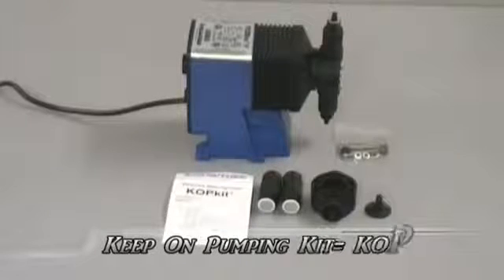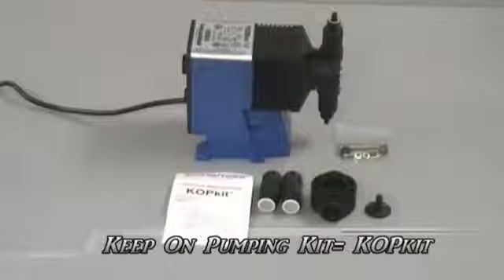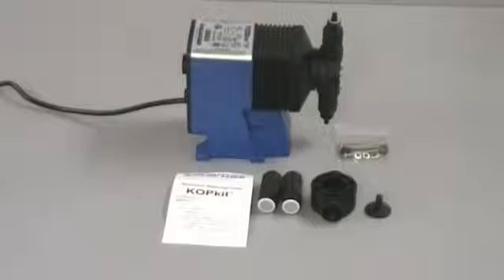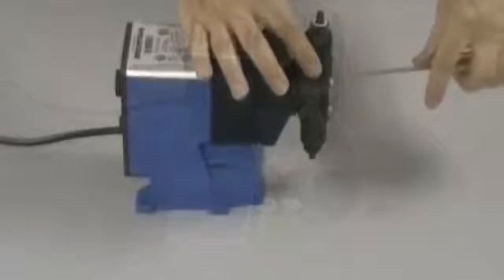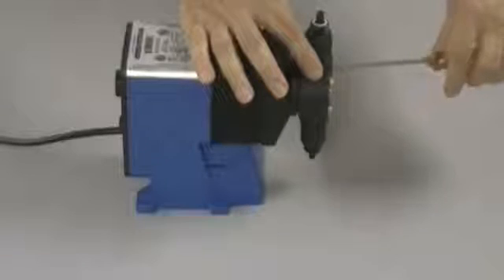Pulsatron keep on pumping kits or KOPkits for short, include the most common items for preventative maintenance. However, other system components such as suction and discharge tubing and all fittings should be checked for potential problems. The first step in replacing the KOPkit is to remove the wet end.